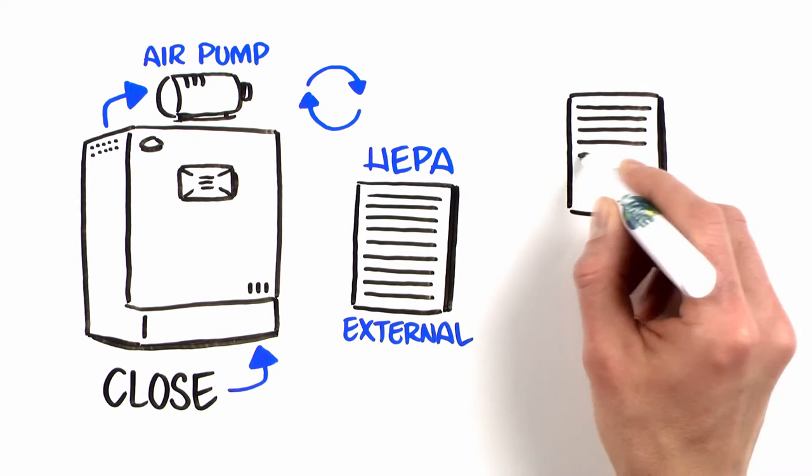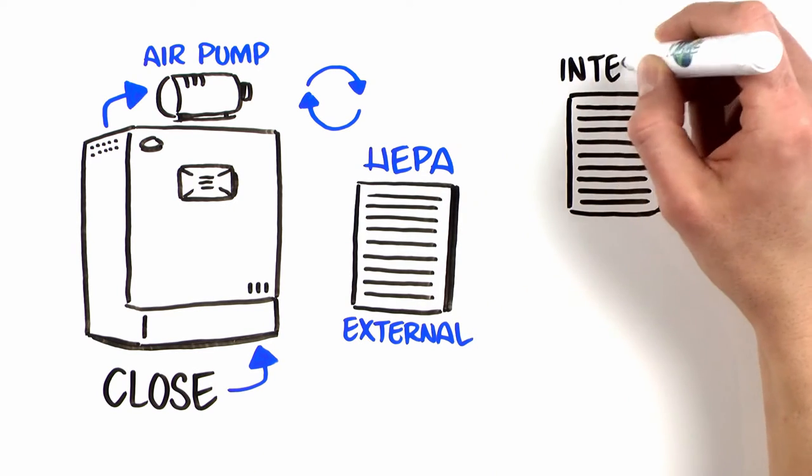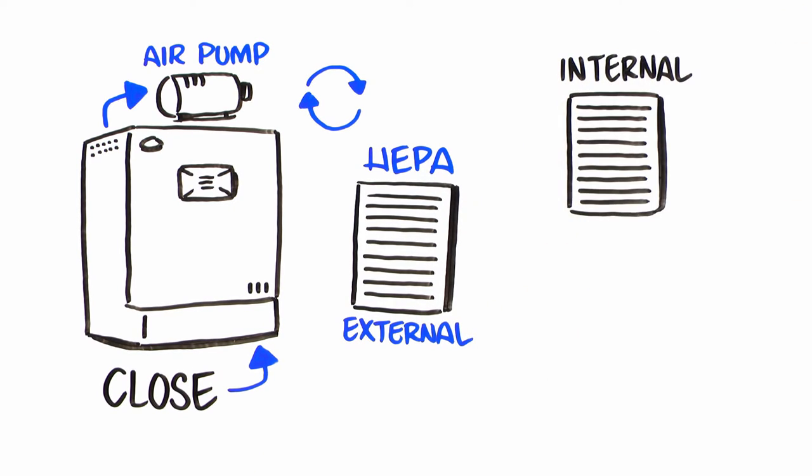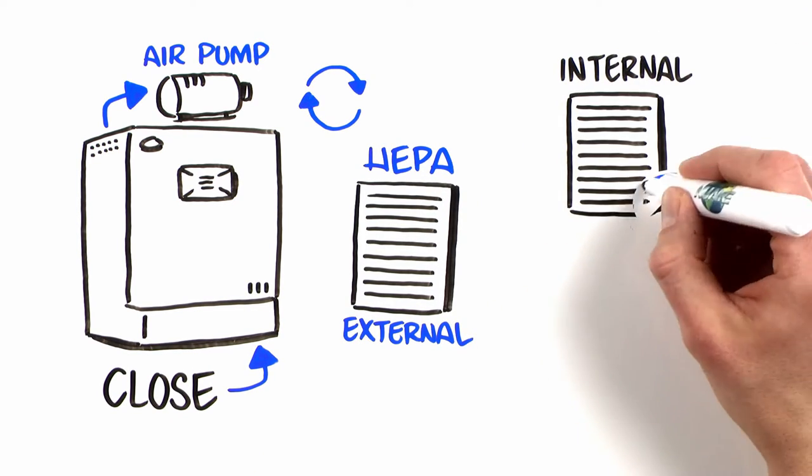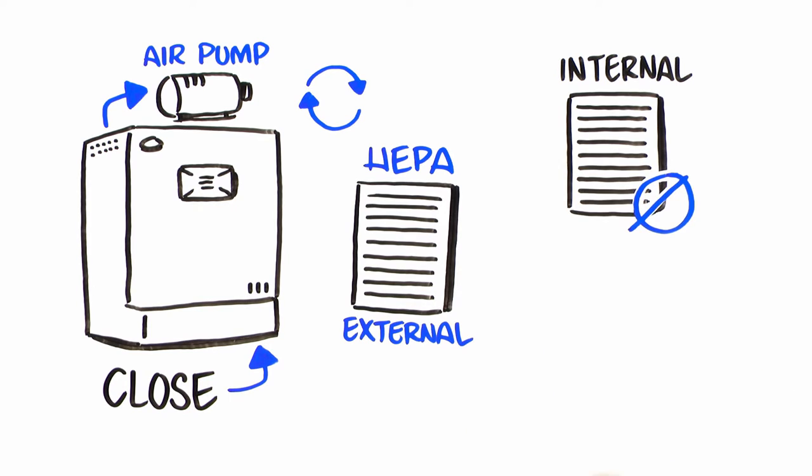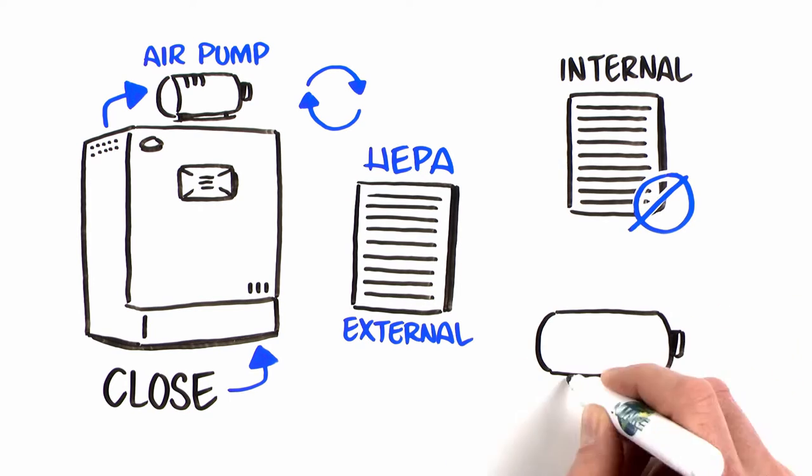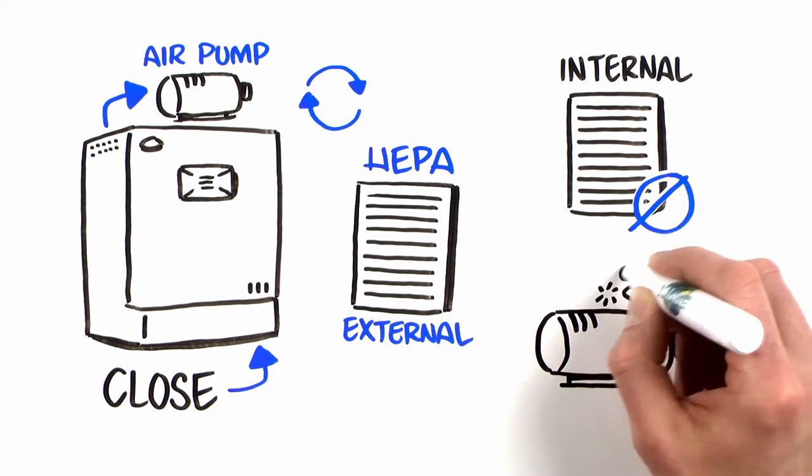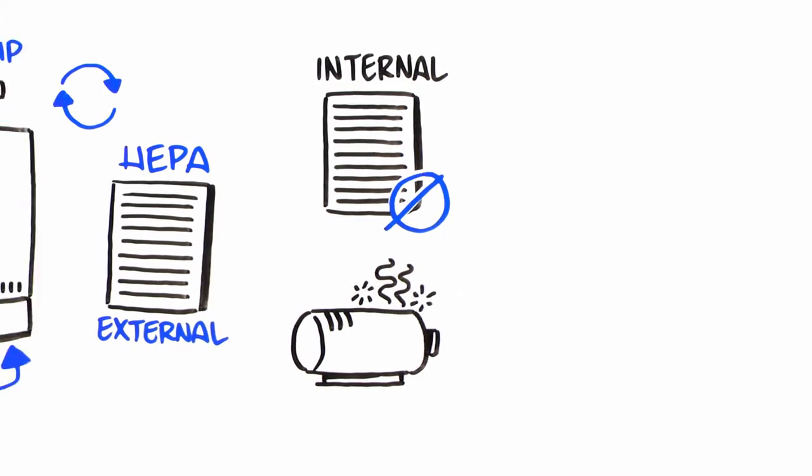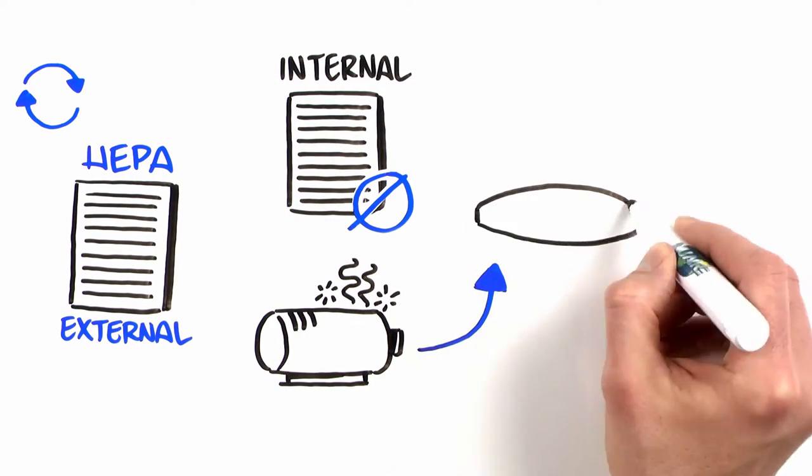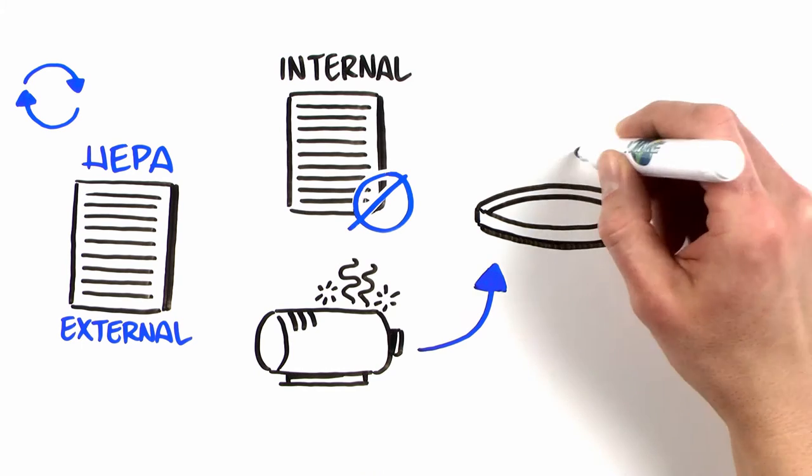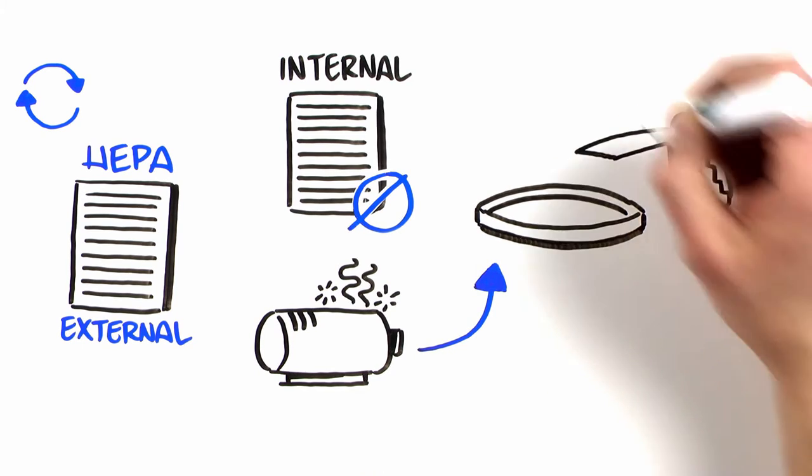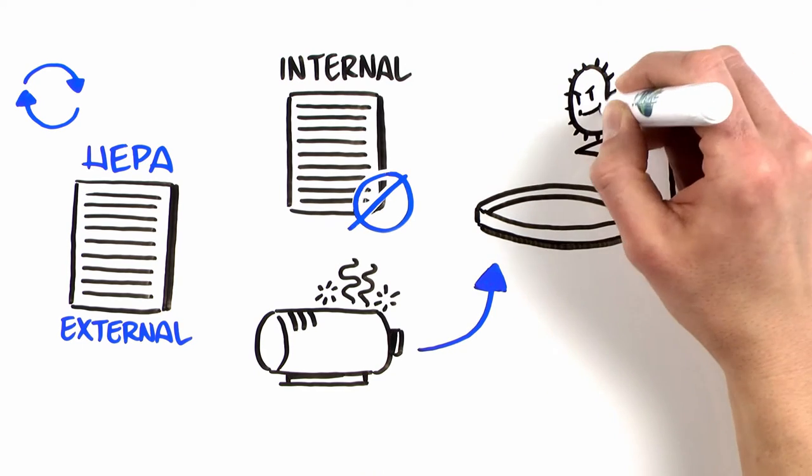Other manufacturers locate HEPA filters within the interior growth chamber. In this case, if the blower motor stops and static pressure is lost, contaminants can fall freely onto your samples.